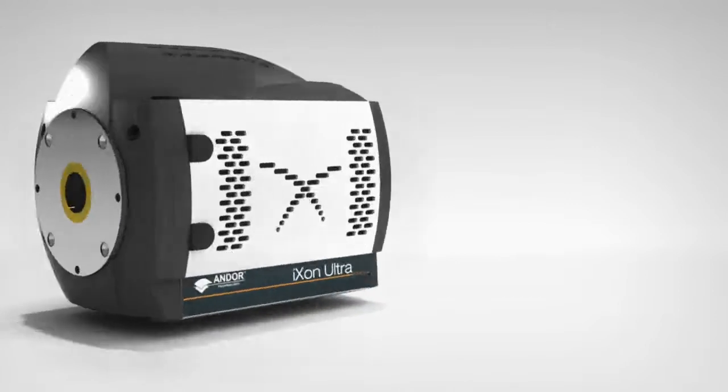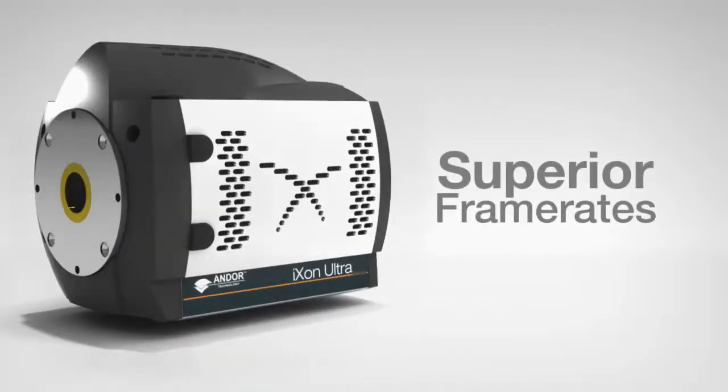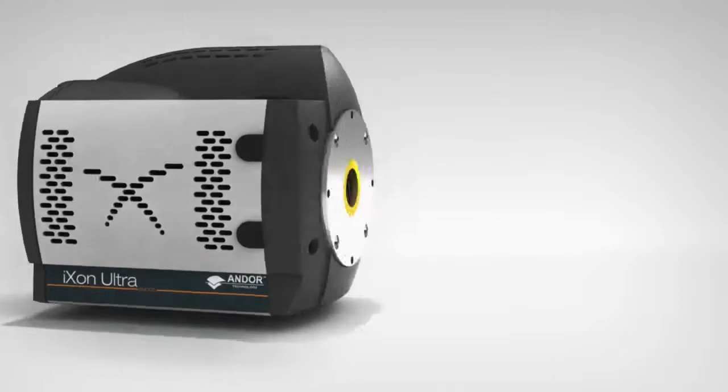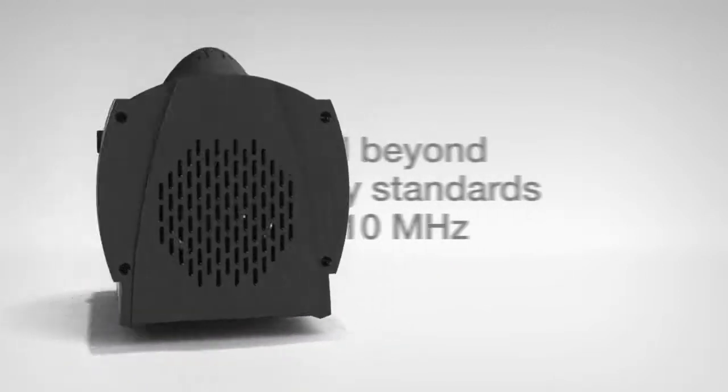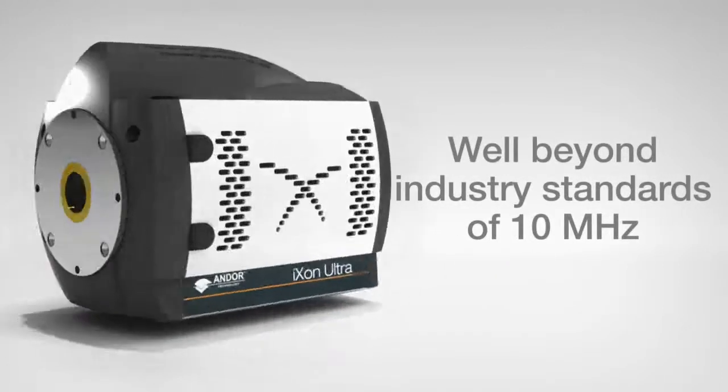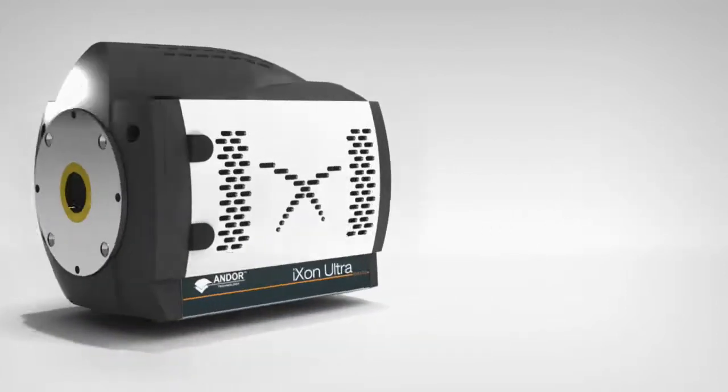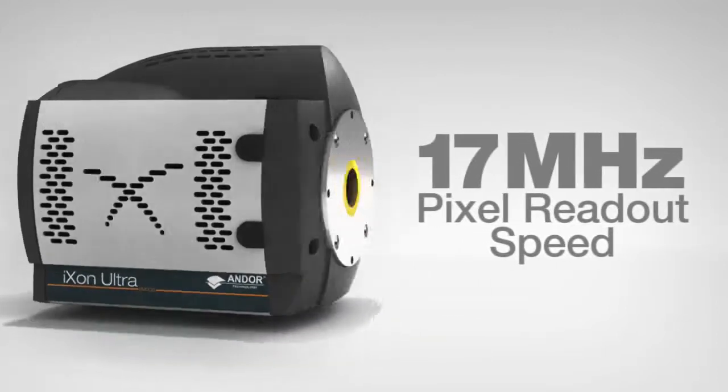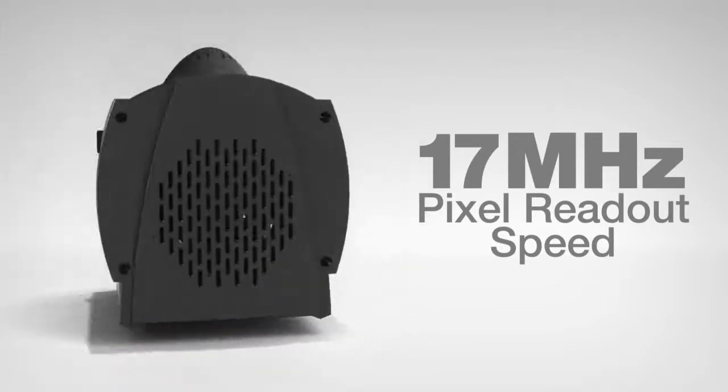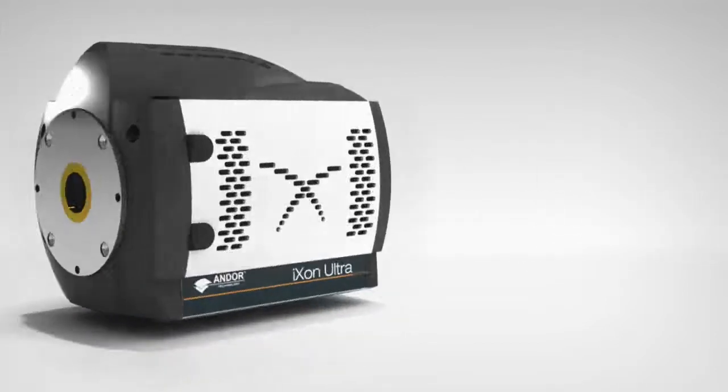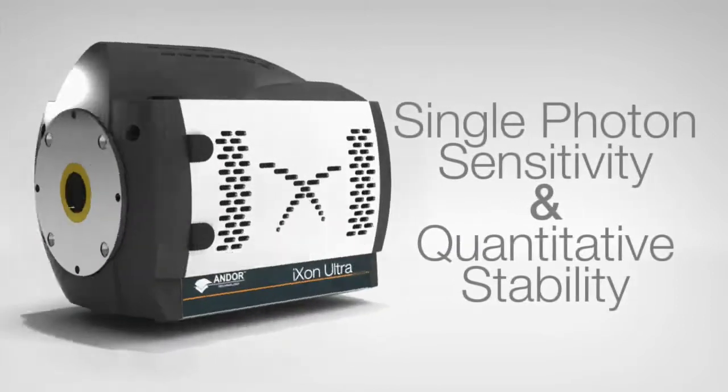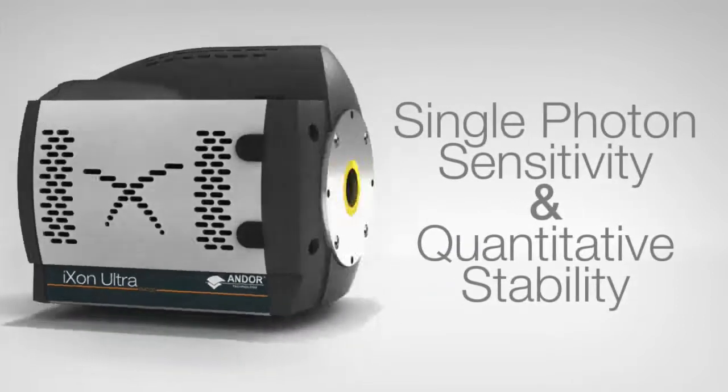So what's new in the iXon Ultra? We've made a number of advances but the most hard-hitting improvement by far is in the frame rate. We fundamentally redesigned the camera to enable us to effectively overclock pixel readout speed to well beyond the current industry standard of 10 megahertz. The new 17 megahertz pixel clock speed that we offer with the iXon Ultra enables the camera to deliver significantly faster frame rates than before whilst maintaining both single photon sensitivity and quantitative stability.